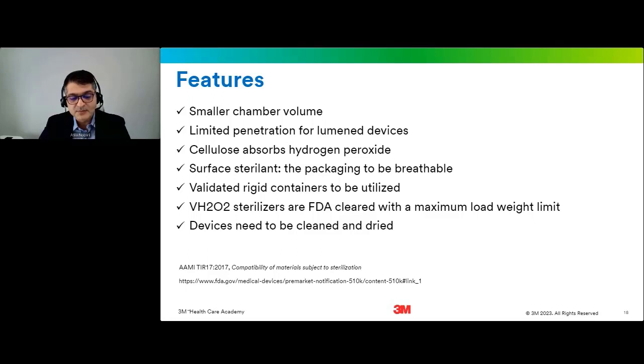Regardless of the sterilization modality and the sterilant's penetration ability, proper cleaning is essential. We cannot forget that. Devices, if they are not thoroughly cleaned and dried, then they cannot be sterilized. That's a baseline. Also, moisture can cause cycle cancellation. So it's important that the devices get dried and cleaned properly.